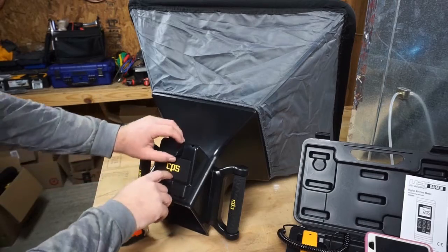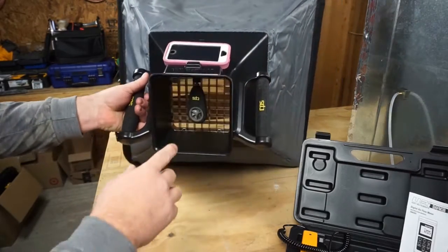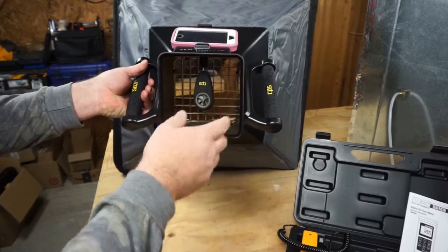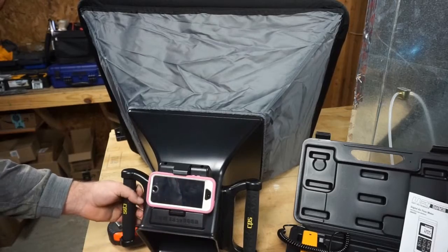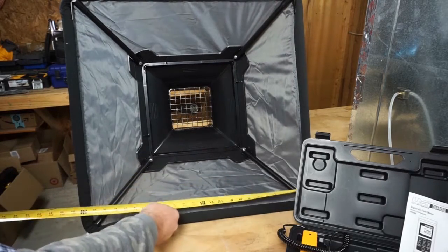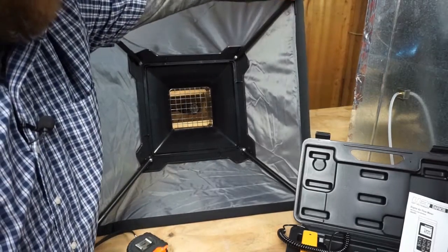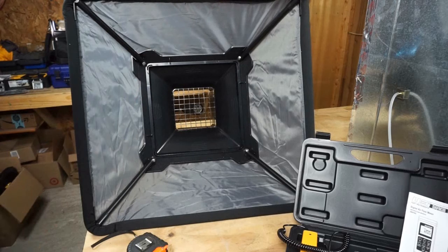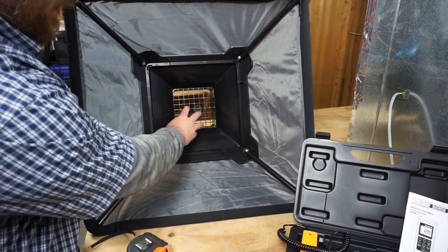The CPS Easy Hood is being shown here. Your phone fits right into it and connects via Bluetooth to the CPS meter on the inside — similar to the old TAB meter. It measures airflow coming through the grid into the funnel with a readout on your phone. The hood is 24 by 24, fitting on a two by two opening, with latches and a foam gasket that makes a pretty good seal.